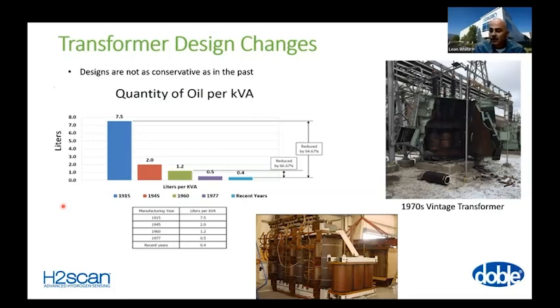We saw the amount of oil per kVA reduced significantly — the amount of oil in a transformer today compared to the amount even in the 60s or 70s is significantly less. So it makes sense that we're going to see transformers, since they're smaller, with tighter clearances, more partial discharge, and more susceptibility to manufacturing issues.